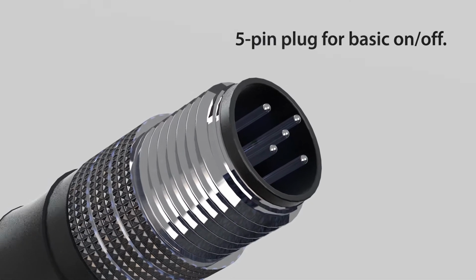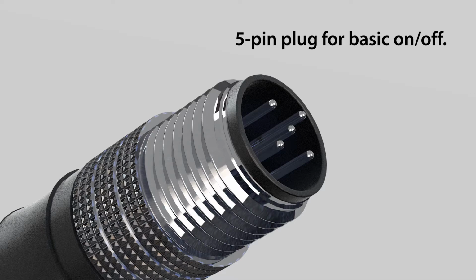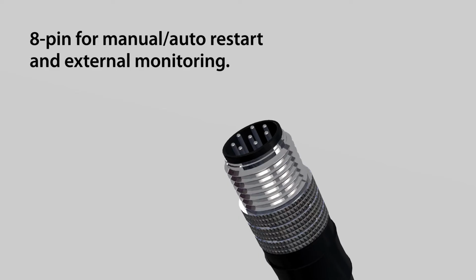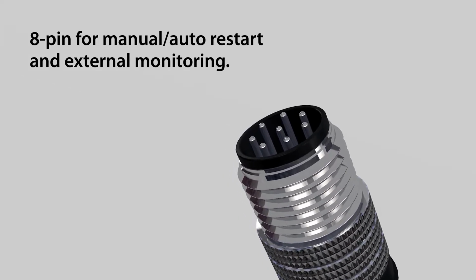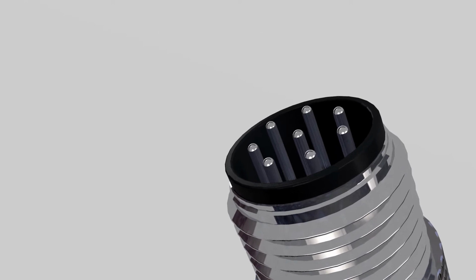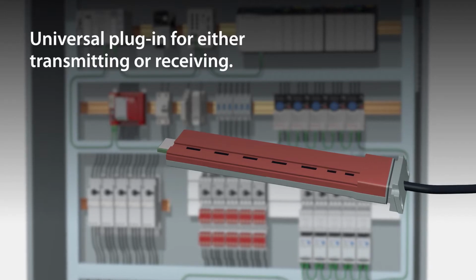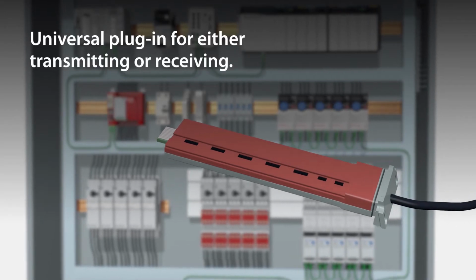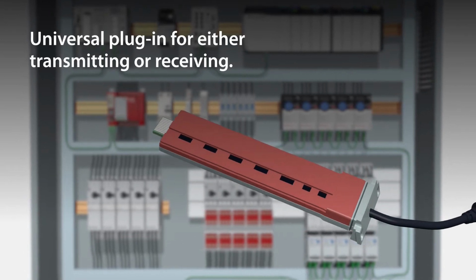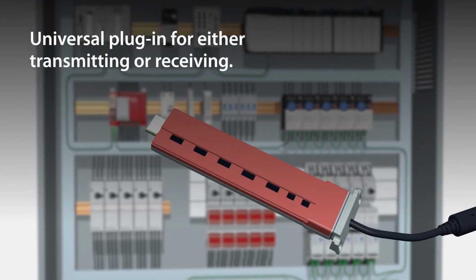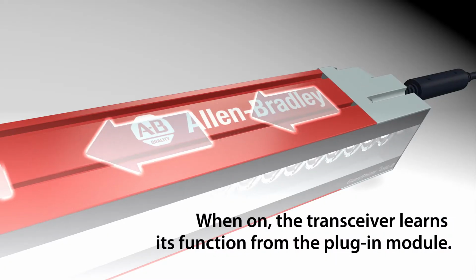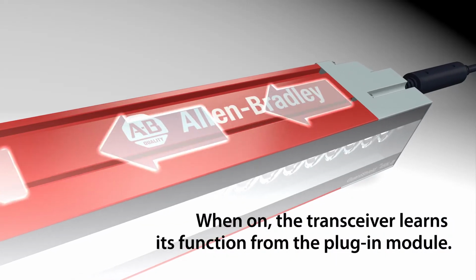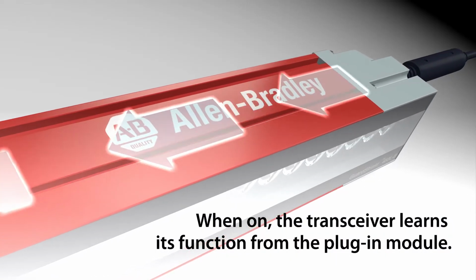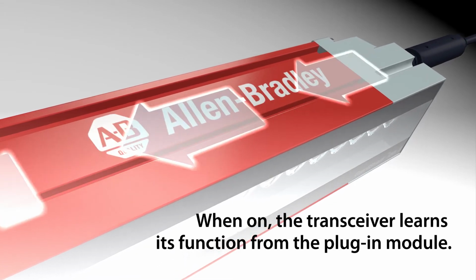Plug-ins are available as 5-pin for basic on-off functionality and 8-pin for manual and auto restart with external device monitoring. There is also a universal plug-in that can be for transmitting or receiving. This feature is set up from your control cabinet.